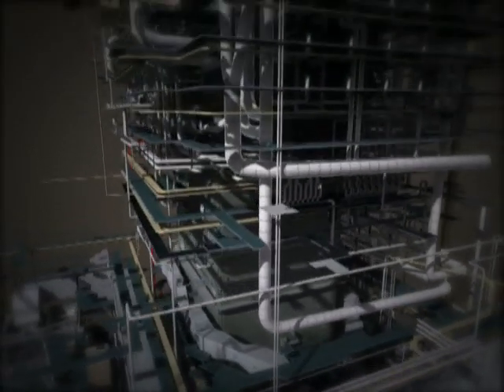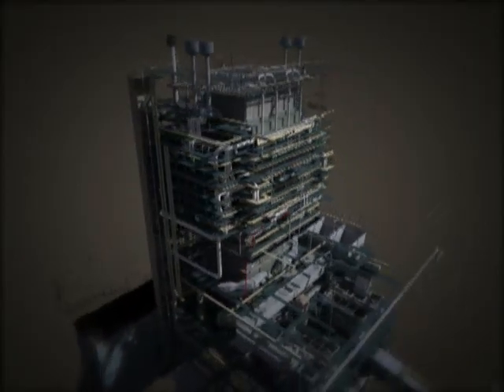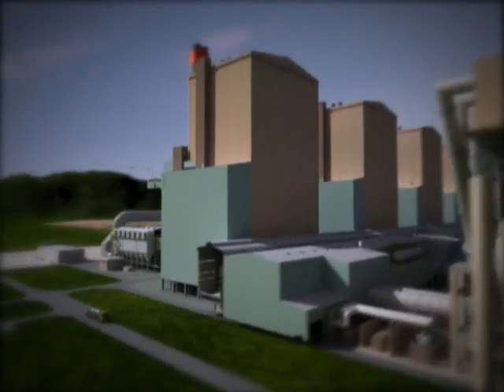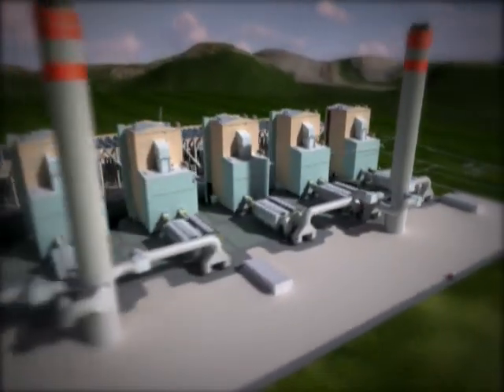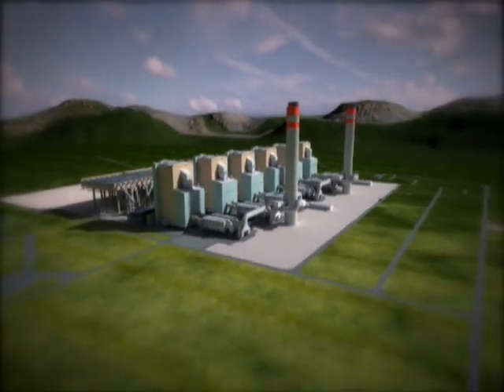There are, however, a number of challenges that are slowing progress, and these are: inadequate planned outages of sufficient duration to carry out testing and inspections to determine deterioration rates, find damaged tubing, and to execute the required replacements or repairs. The availability of skilled engineers on site to determine the root cause of the failures and develop testing techniques. The poor condition of some of the boilers. Overcoming these challenges will make it possible to achieve our targeted performance and support Eskom in becoming one of the top five performing power utilities in the world.